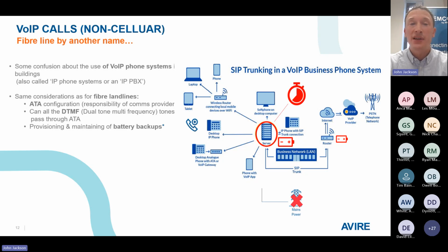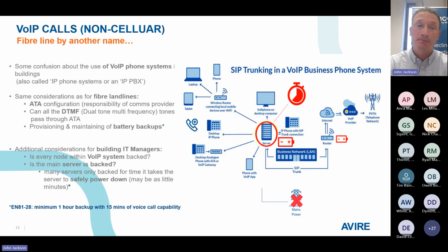As a business, we've seen several examples recently where, when clients have done due diligence on this, it turns out to be like 6 minutes of backup - not enough to provision an alarm call within the minimum required standard. I think this is where it falls over. It can work in some instances, but in many others, getting the guarantee that all the devices involved in commissioning the call have enough battery backup to enable standards and regulatory compliance is difficult.